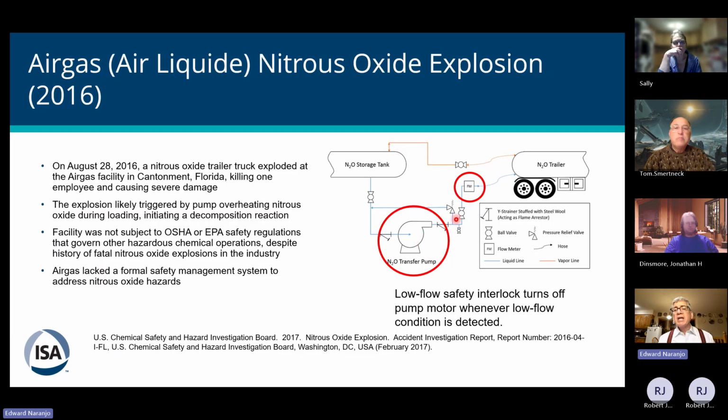The system, as I pointed out, is very crude. You have a flow rate, but there really is no means to detect the degradation of the flow meter itself. If you have studied functional safety, you know that for many systems there need to be safeguards, but safeguards themselves are not enough. Any safeguard over time will degrade, and so there has to be a means to either replace or arrest the degradation of the safeguard. That was just not the case here.